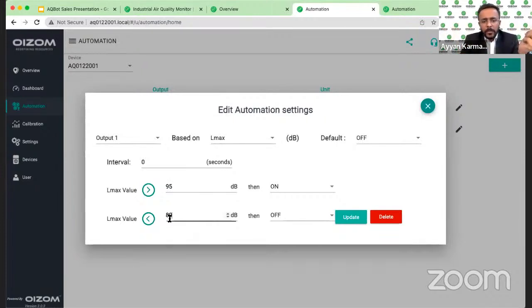And similarly, to go below that, I'm going to set it at 90. So what this means is that when the value goes beyond 95, the relay will trigger a third-party equipment, and when the value reaches 90, it will trigger the equipment to turn off.